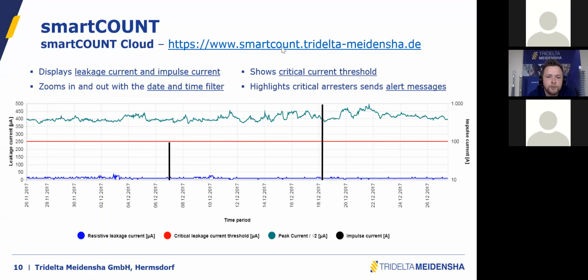And we have the blue line, which is the resistive current, which has been calculated from the third harmonic of the surge arrester leakage current. And of course, this resistive leakage current is always lower, much lower than the peak current itself, as long as the surge arrester is healthy. So this looks like a healthy surge arrester with very, very low resistive currents.